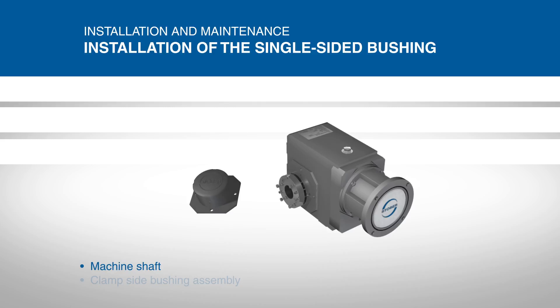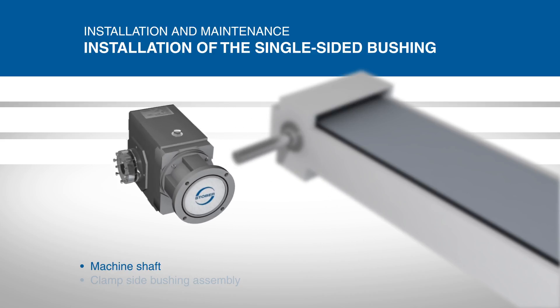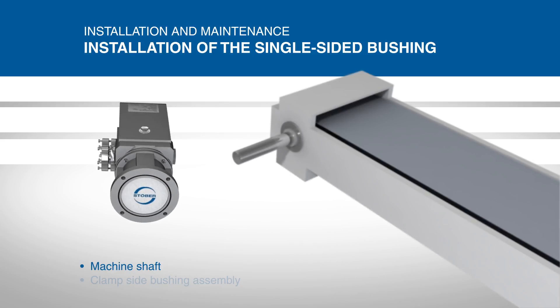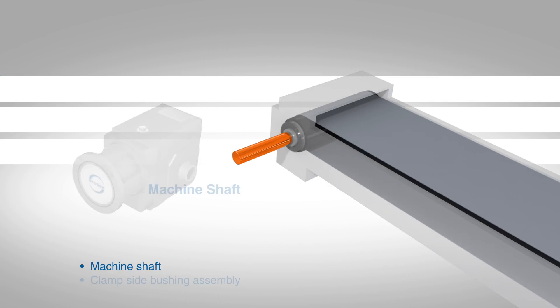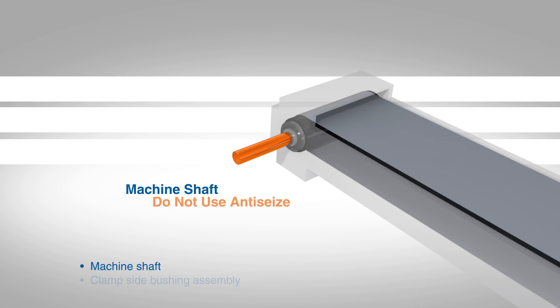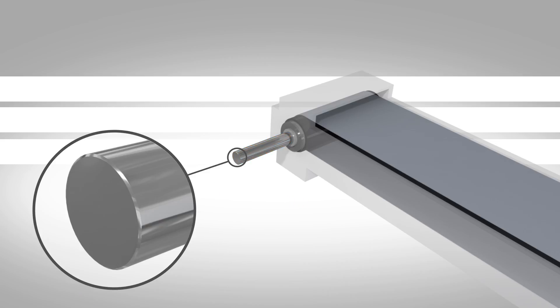Before installing the reducer, clean the machine or conveyor shaft with a shop towel or soft cloth to remove any residue. Do not use any type of anti-seize on the shaft or bushing. A 1/32 by 45 degree chamfer at the end of the shaft is recommended for ease of installation.